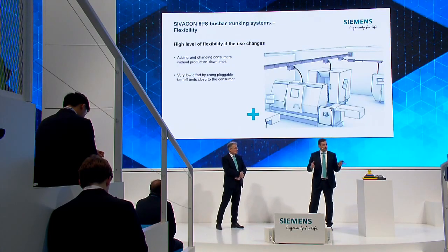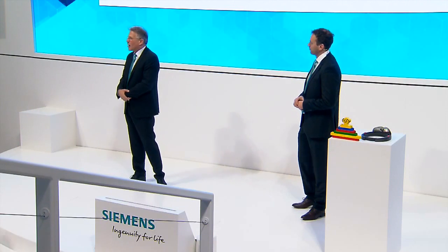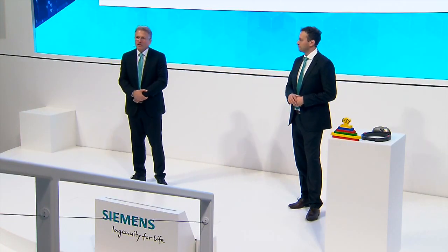Now you see, the SIVACON system is very flexible. But the major question is if this doesn't increase the complexity of the planning phase. Not at all, because Siemens is offering the right tool for every phase, and they are working hand in hand with each other. SIMARIS design, for instance. SIMARIS design is designing your electrical grid, considering short circuit ratings, voltage drop, and other issues like selectivity, for instance.